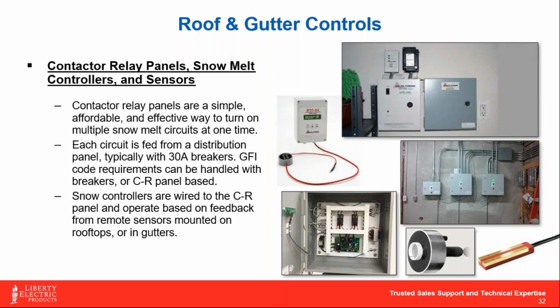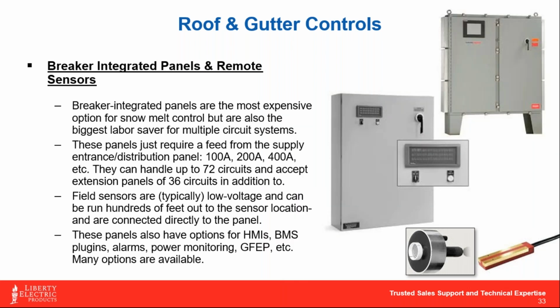We can put timers into these as well, so that after the sensor has cleared itself, after the water's evaporated off the surface of the sensor, it can continue to stay engaged for anywhere from a half hour up to, you can literally put it into a 24-hour loop schedule. So again, very logical, very simple in terms of their functionality. And we like the fact that a lot of these manufacturers actually don't give you too many options that you can play around with and kind of screw it up.